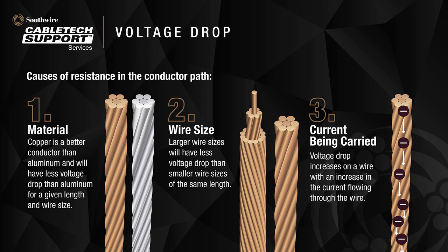Let's review the causes of resistance in the conductor path. First, the material — copper or aluminum. Copper is a better conductor and will have less voltage drop than aluminum for a given length and wire size. Second, the wire size — larger wire sizes will have less voltage drop than smaller wire sizes of the same length. Third, the current being carried — the voltage drop increases on a wire with an increase in the current flowing through the wire.